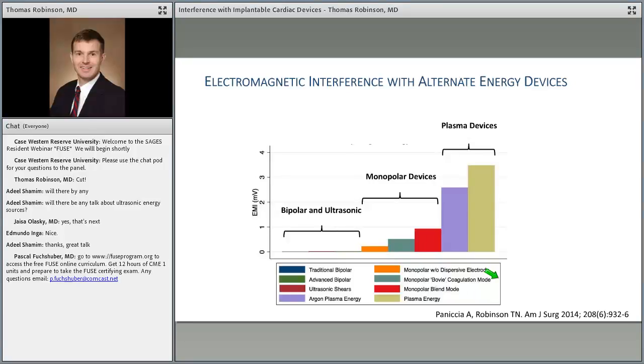The plasma devices are the worst. So what is a plasma device? That's like the argon beam, right? The argon beam has a spark gap between the tip of the active electrode and the tissue. You need a lot of voltage to get that energy across that spark gap. So this is going to be your highest one. So you really probably should avoid the argon beam and the plasma devices.